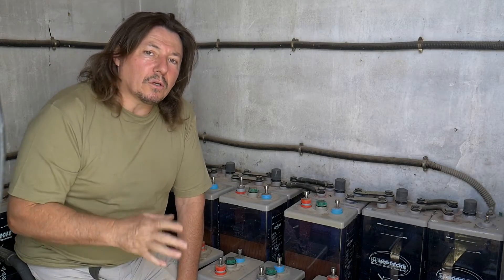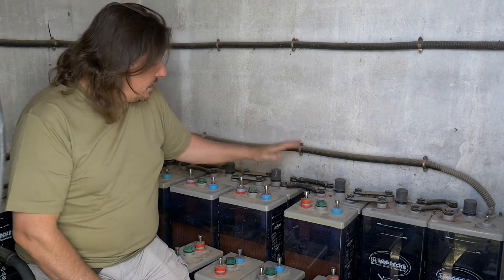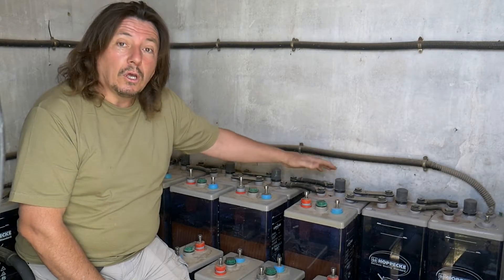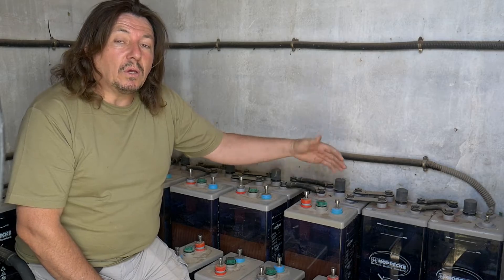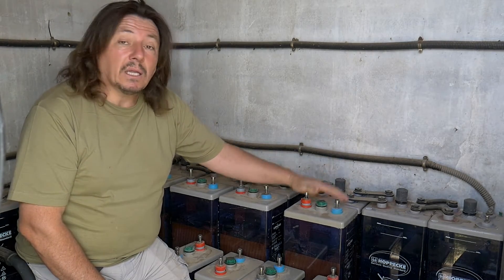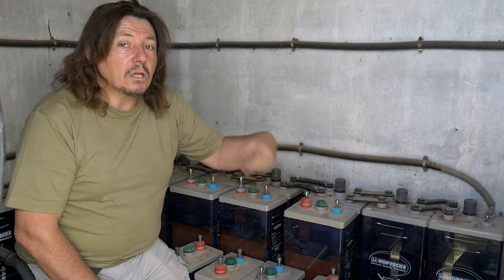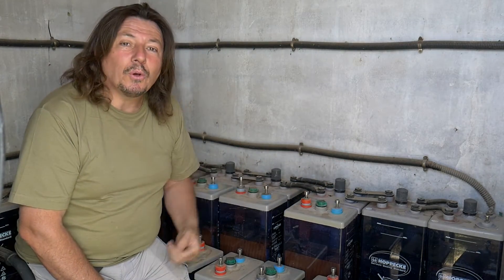Good day! You've got a source system, you've got a bank of batteries, and you'd like to add another one but don't know how to connect it correctly. For instance, I've got a 24 volt system — if you connect it wrong it will give you a 48 volt battery. What I will do is connect another set of batteries to double the size of my battery without going to 48 volts. I will keep 24 volts and show you how to do it.